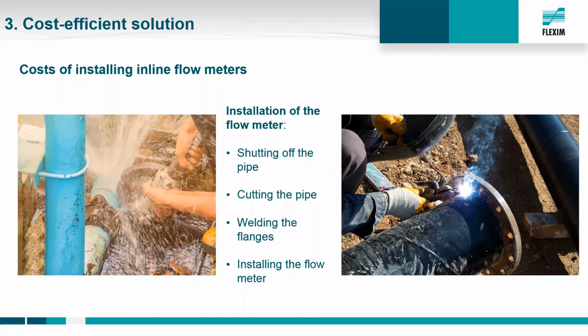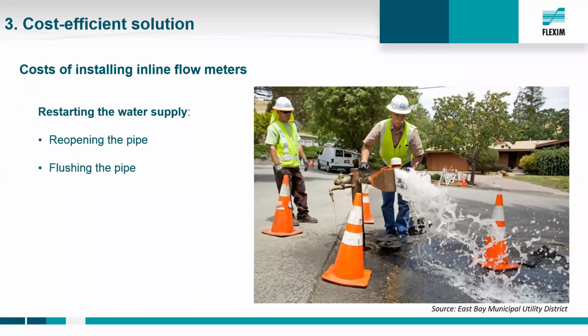On these nice exemplary pictures here, we see small pipes. It's not really often water mains. Water mains usually are bigger, so considering a DN600 or DN800 line, even putting a big inline meter in place needs pretty big effort, some staff, and heavy lifting equipment. Coming to the end of the implementation, everything is set, the flow meter is in place and commissioned. Then we have to reopen the pipe, ensure the supply again, and flush the pipe because we have done intrusive works.